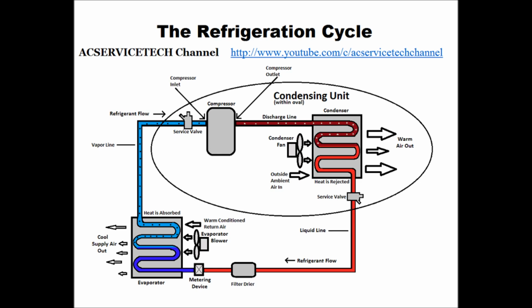So what you have is a low pressure, low temperature vapor coming into the compressor, and then high pressure, high temperature vapor coming out at its hottest point. Then it enters the condenser coil where it starts to reject heat until it becomes a saturated state where vapor and liquid both exist. After that, it rejects more heat as a liquid. It's out of its saturated state, turns into a liquid, and continues to drop in temperature until it comes out past the valve. That is called the subcooling, the temperature decrease in liquid form.